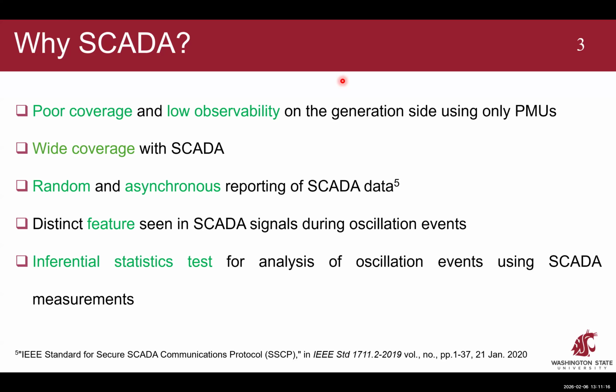Then, how can we use SCADA for analyzing oscillations? Because we know from the sampling theorem, we need a scan rate at least twice as fast as the oscillation that we are observing to capture the information from the oscillation, in a theoretical sense. Whereas if we say 10-second SCADA rate, that is, roughly speaking, 0.1 hertz, so it would seem appropriate for only oscillations 0.05 hertz or slower. But we know the typical oscillations are much, much faster than that.